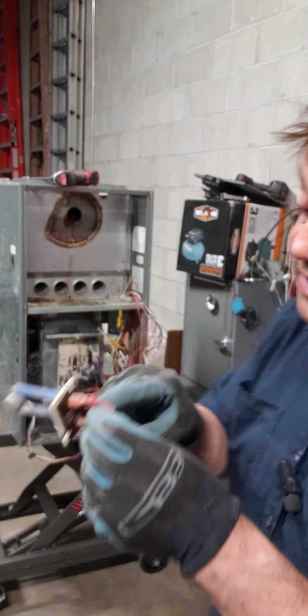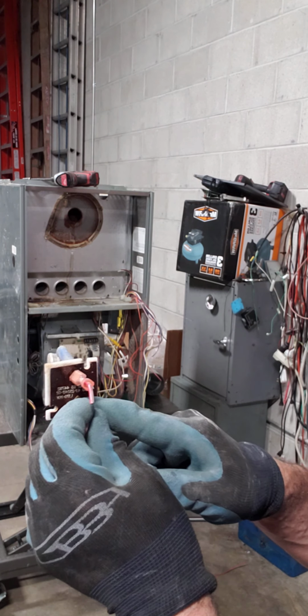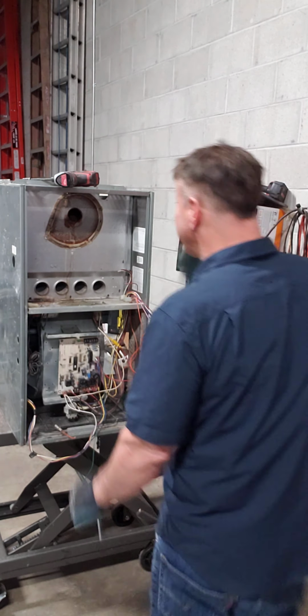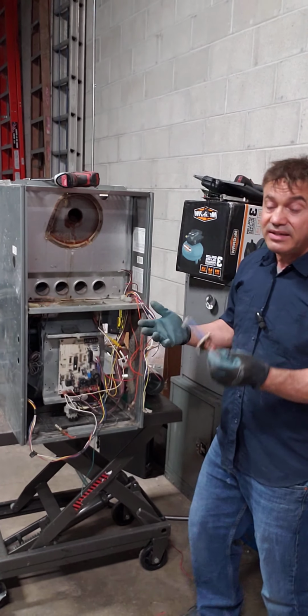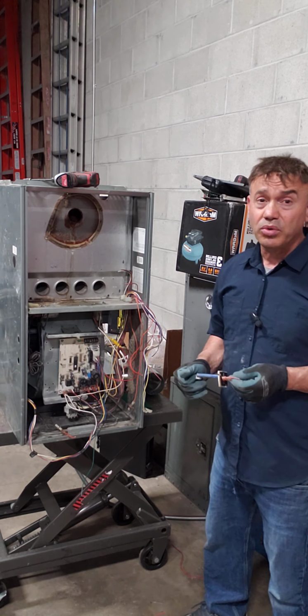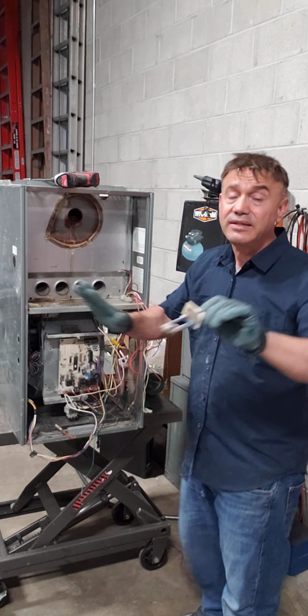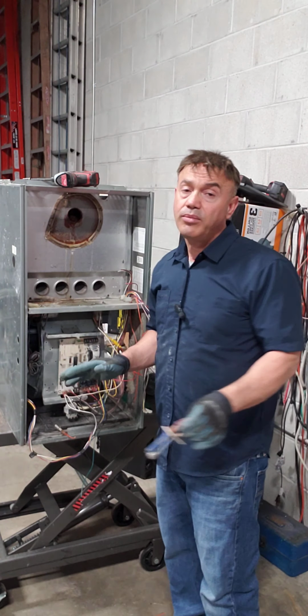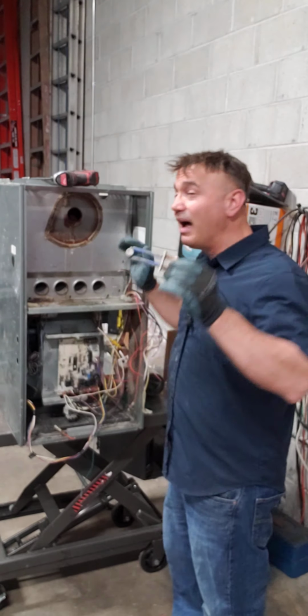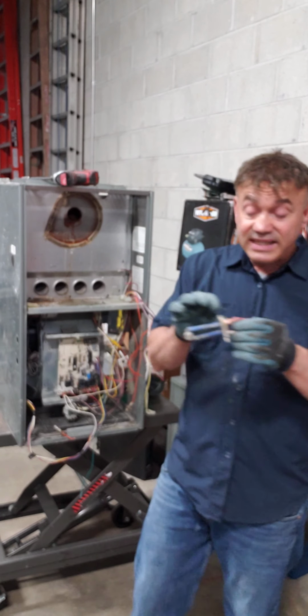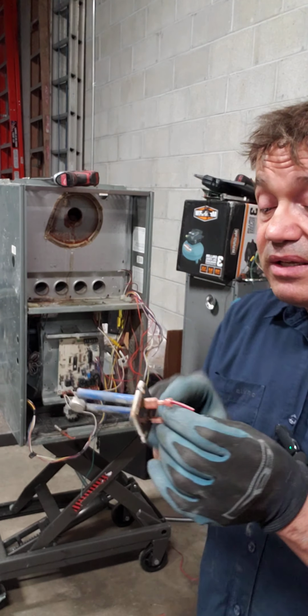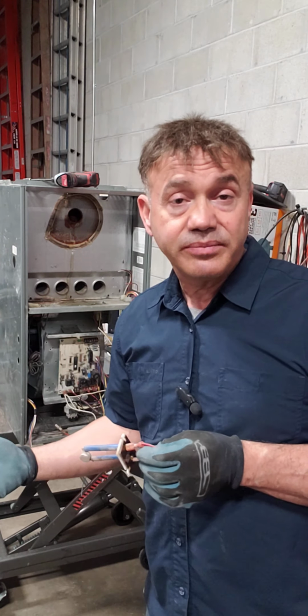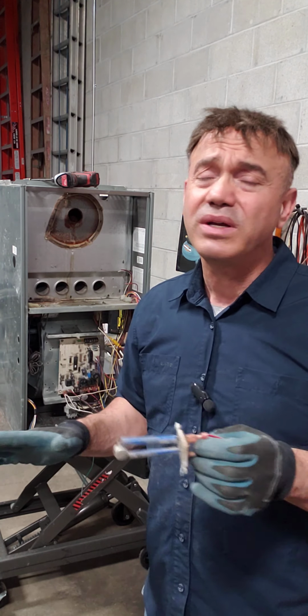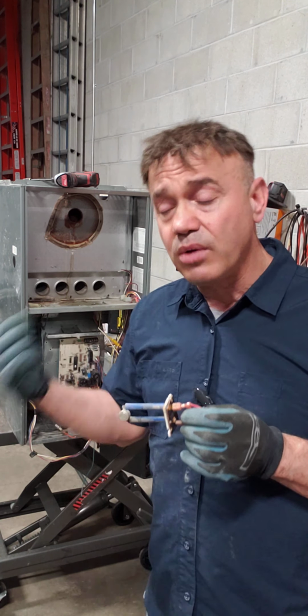overheat, and this guy is gonna monitor the temperature. We said 170. Let's say it goes to 180, 185, and then the limit will send the signal to the control board: hey, stop, stop, stop. It's getting too hot. It's so dangerous. Control board, I'm so sorry, don't be mad at me, I'm going to have to interrupt everything. And then immediately when the heat limit opens, the blower will come on no matter what. It will force it, so it's going to cool down the furnace.